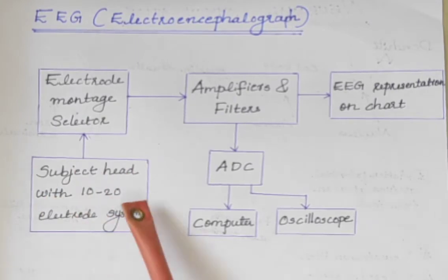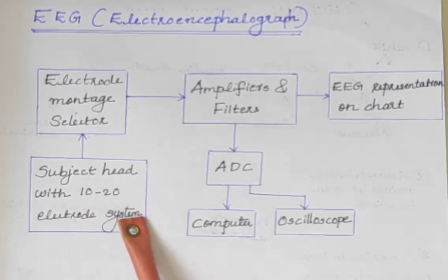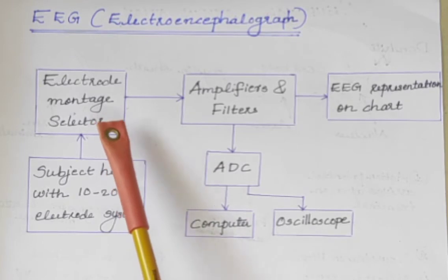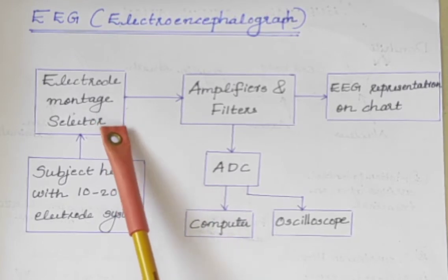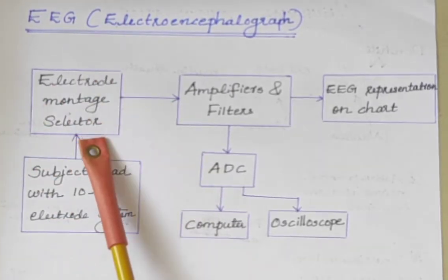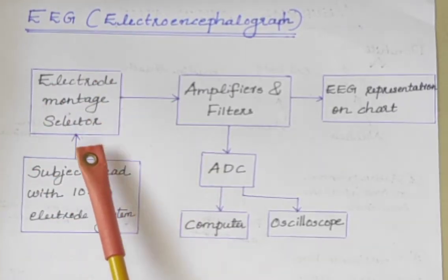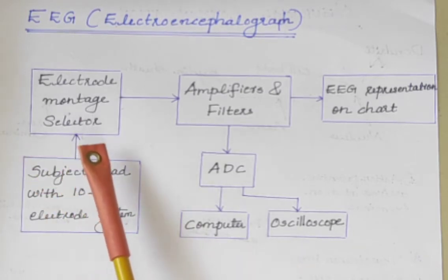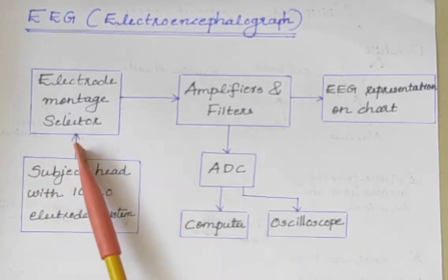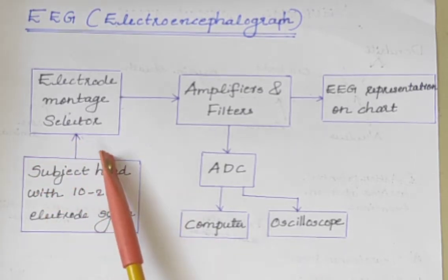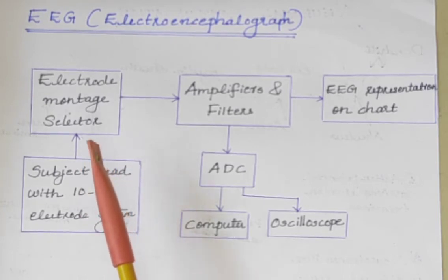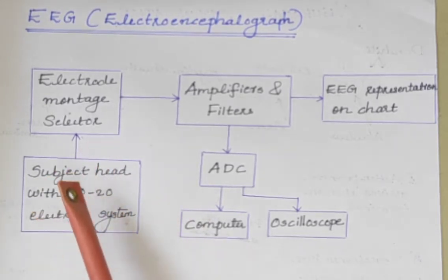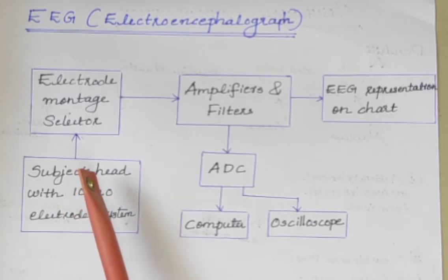Next is the electrode montage selector. EEG signals are transmitted from the electrodes to the montage selector panel. The montage selector of an EEG machine is a large frame which consists of different switches, so as to allow the user to select the desired electrode pair.